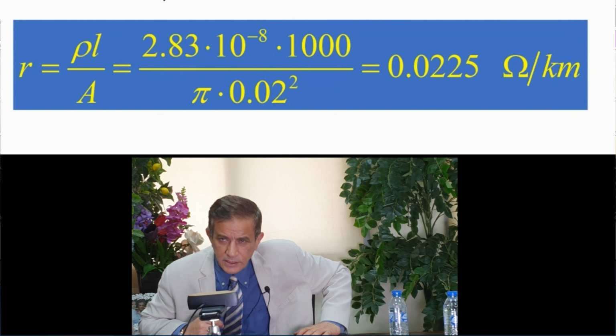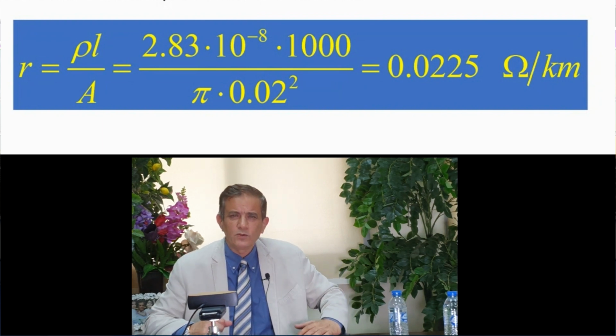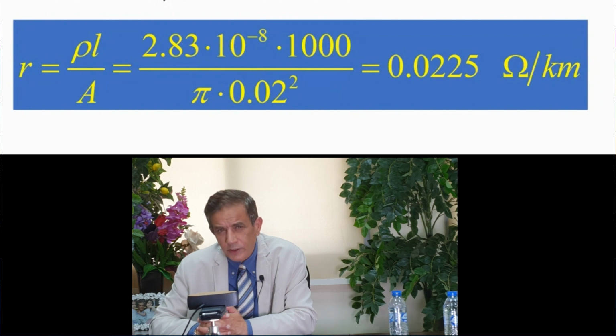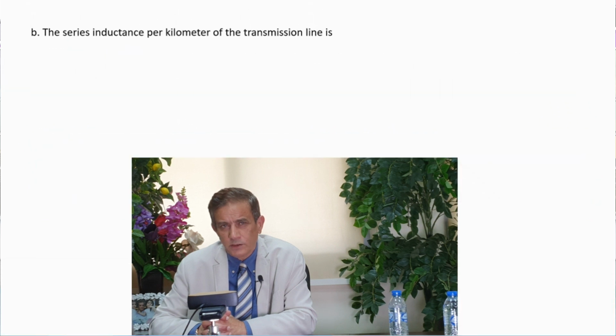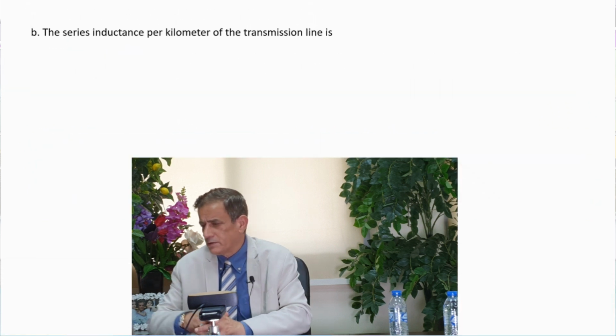Small r is the resistance per unit length. I find small r using rho over A, multiplying by 1000 to get it per kilometer, since the length of the transmission line is given in kilometers. This gives 0.0225 ohm per kilometer, which is the series resistance of the transmission line.